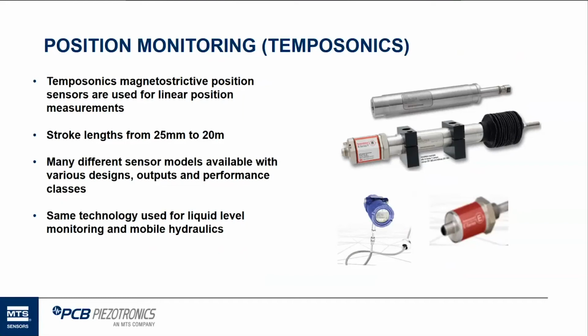They use a magnetostrictive technology sensor. So it's basically a magnet on a shaft that moves depending on the type of sensor it is. It moves on a shaft, providing an output based on the magnetostrictive position. The sensors provide a lot of different types of outputs: analog, voltage outputs, and digital outputs. Just about any type of Industry 4.0 output you could think of is available with the TEMPOSONICS position sensors. This same technology is used in the liquid level sensors as well. It's just a different type of sensor that can be mounted within liquid.